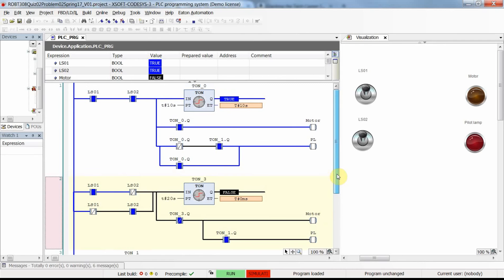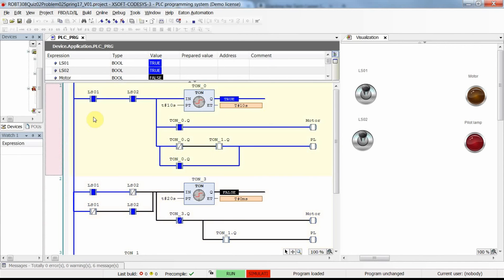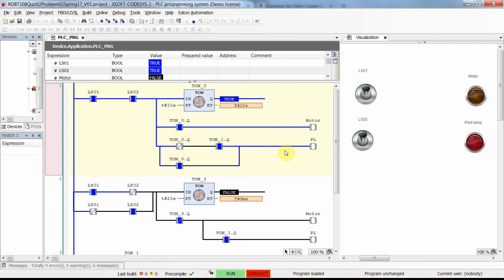This second rung prevents the first rung from executing correctly. We could change the order, putting the second rung first, but then only the second one works properly and not the first. The order in which rungs are placed is critical, especially when coils appear in multiple rungs determined by different input conditions.